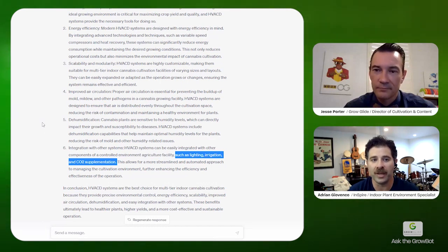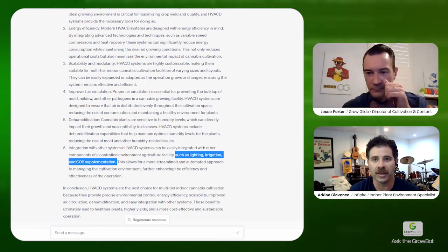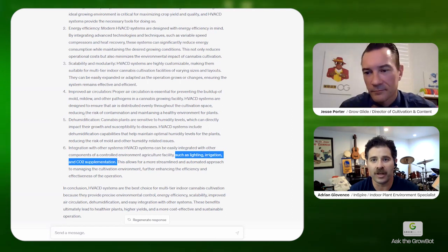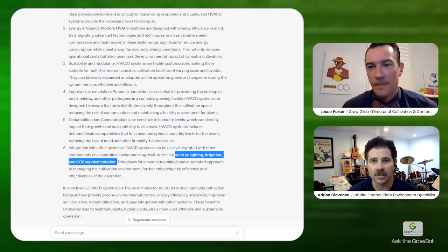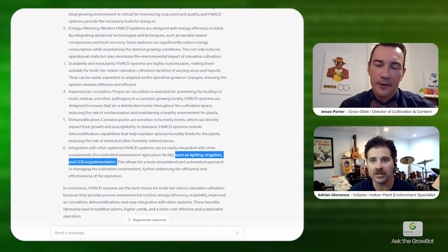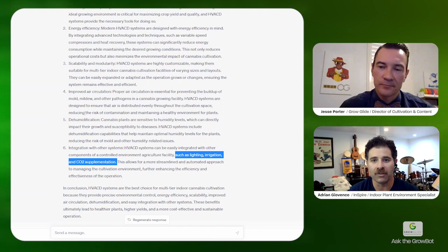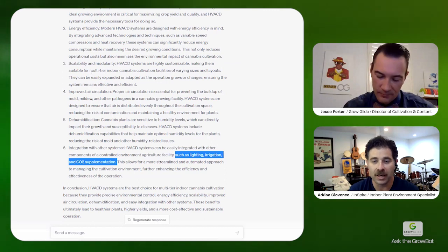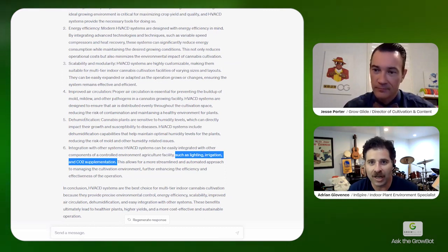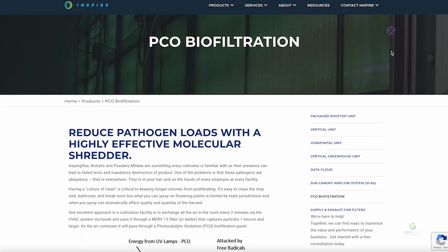To me, that's one of the biggest differentiators with an integrated system—we're taking the air back in a warm, humid condition, cooling it down, and then reheating it back up before it goes to the plants, so that you're delivering it to the plant canopy within the parameter you're looking for—call it 75 to 80 degrees, or 70 to 82 or 85, wherever we're at in that wider range. But at least we're then delivering room-neutral temperatures back to the plants. And oh, by the way, it can be CO2 rich, and it can have gone through air cleaners, like you mentioned, and other things—so there are other benefits and byproducts of it.